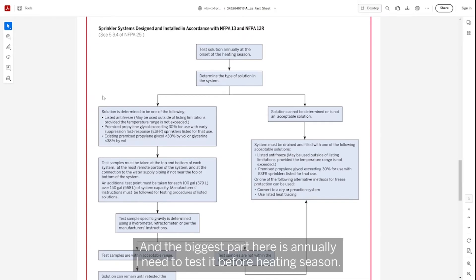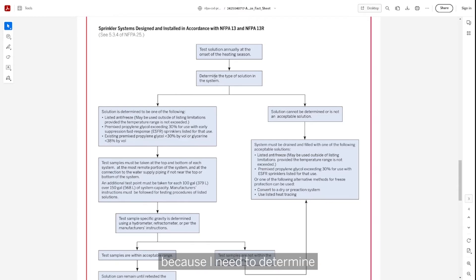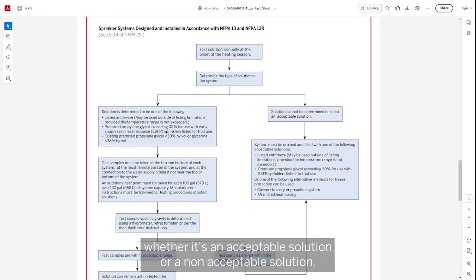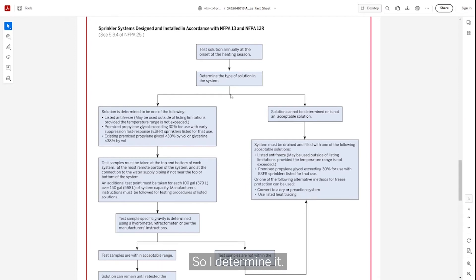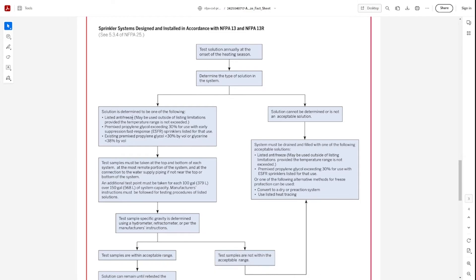And the biggest part here is annually, I need to test it before heating season. And I need to determine what type of solution I have because I need to determine whether it's an acceptable solution or a non-acceptable solution. There's kind of only two options here. Either it's acceptable or it's not.